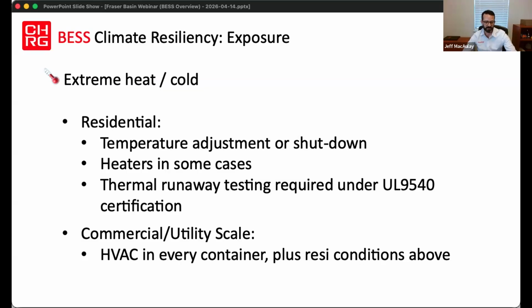That HVAC is driven by the battery itself, so you're plugging in the battery and the whole storage container operates as a unit. Often the inverters are inside that container in smaller applications, and in the Tesla example shown, they're external. But in all cases, the container is managed from an HVAC perspective to ensure maximum operating range, typically down to -30 or below, all the way up to above 40 Celsius.